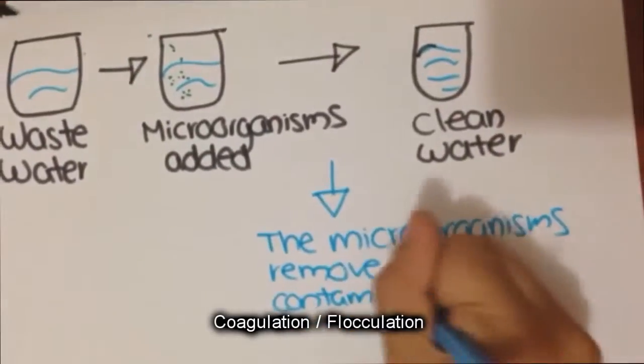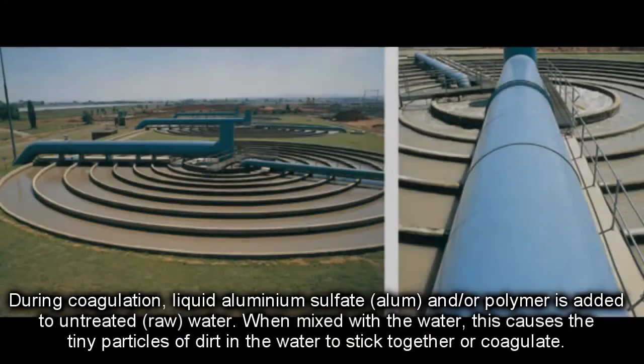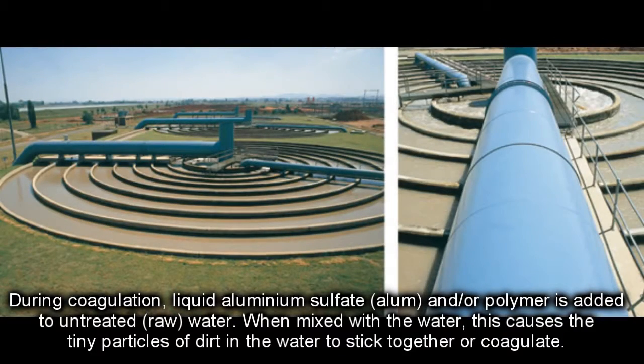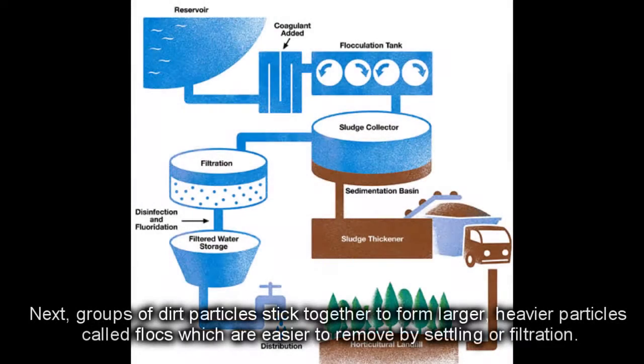Coagulation and flocculation. During coagulation, liquid aluminum sulfate or polymer is added to untreated water. When mixed with the water, this causes the tiny particles of dirt in the water to stick together, or coagulate. Next, groups of dirt particles stick together to form larger, heavier particles called floc, which are easier to remove by settling or filtration.